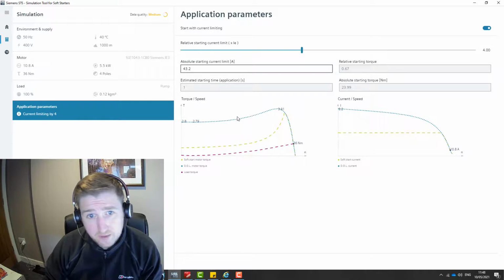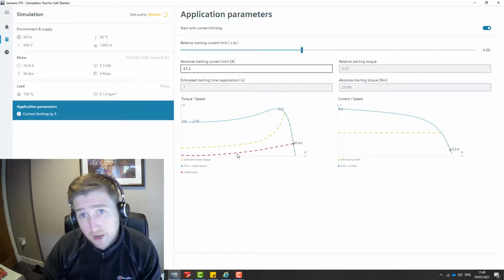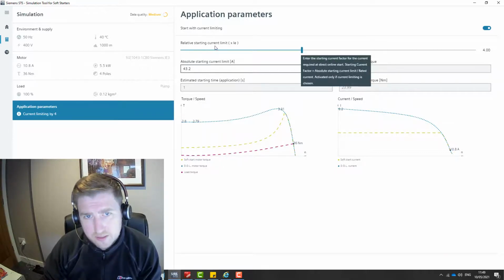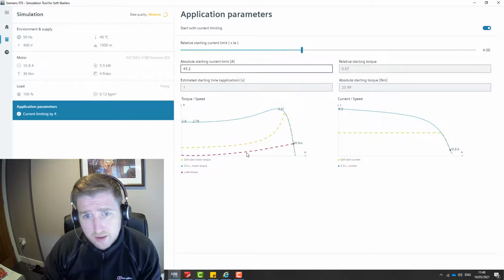As you can see here, you've got two graphical representations, one for torque and speed, one for current and speed. On here, you've got the soft starter simulation, which is this yellow line. You've got a DOL, which is this blue dotted line, and you've got the load torque line, which is here. The idea is that we can now optimize our motor startup before we've even purchased the unit. So we now know what to set the potentiometers to. This first pot here is for the starting current, and the idea is that this yellow line can't intercept with the load line, because if it does, the motor won't start.